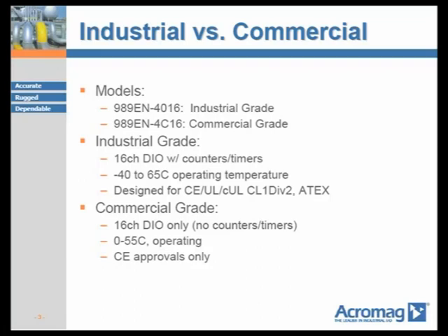The Model 989EN-4C16 commercial grade instrument is simply a basic 16-channel Ethernet discrete I/O module. It does not include any counters, timers, alarms, or hazardous location approvals. The continuous operating temperature for the 4C16 unit is rated at 0 to 55 degrees Celsius. This unit is ideal for OEMs, commercial, and light industrial markets and industries.